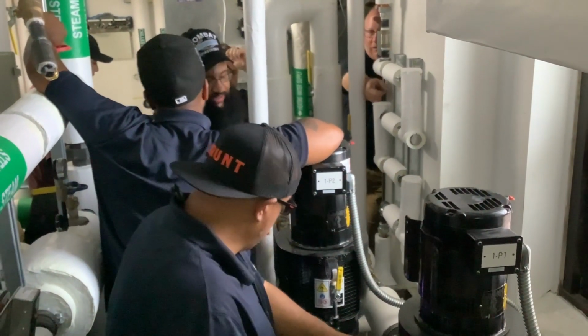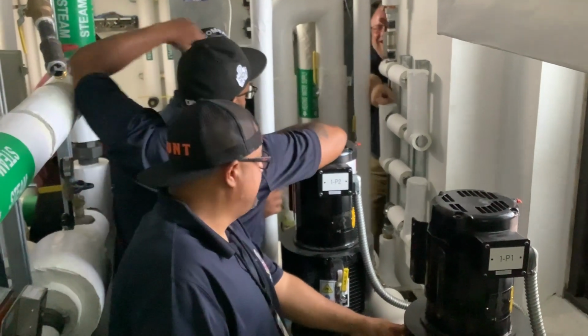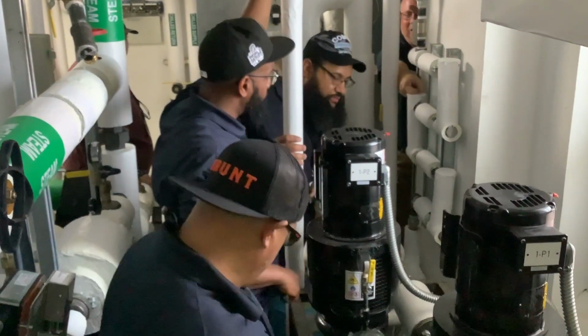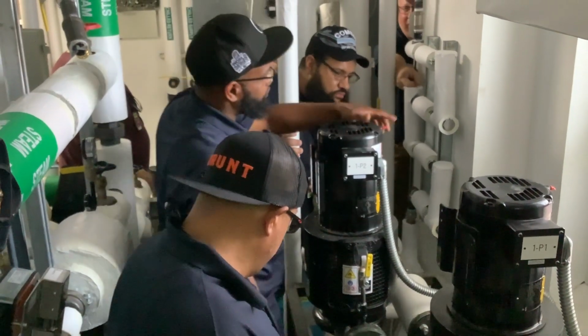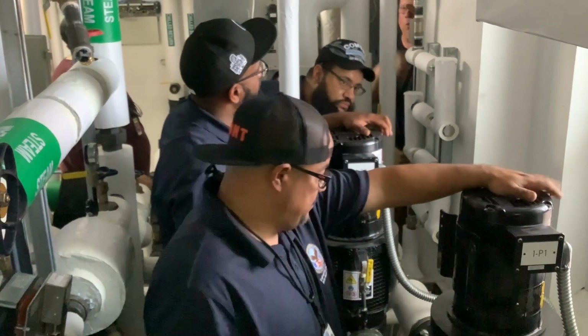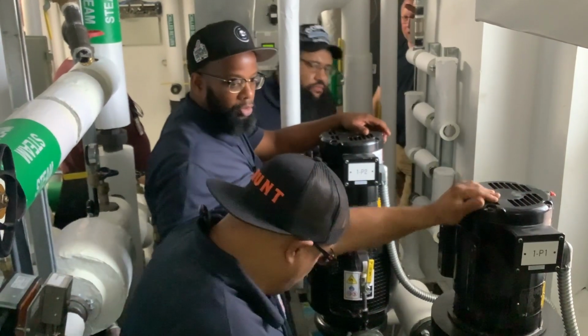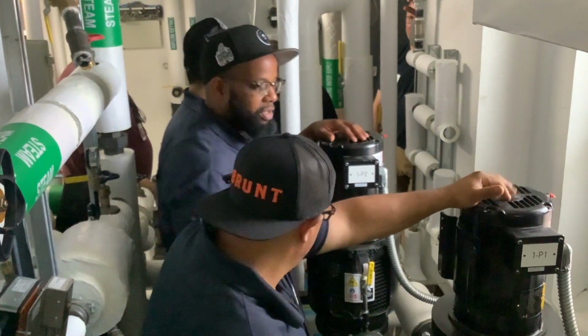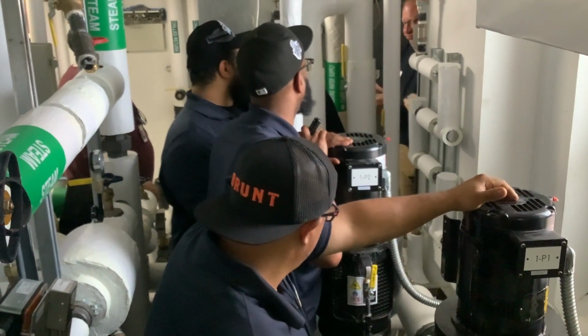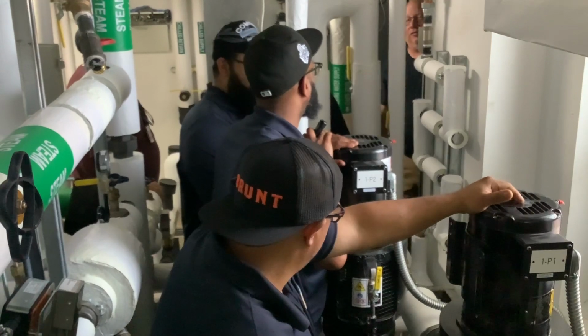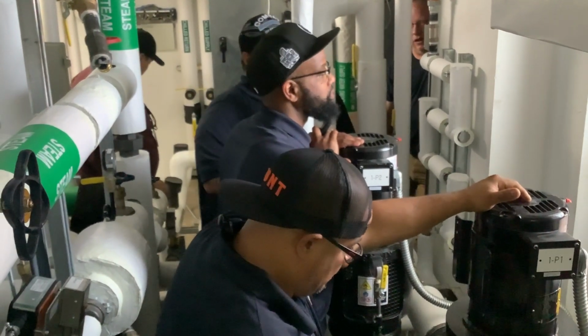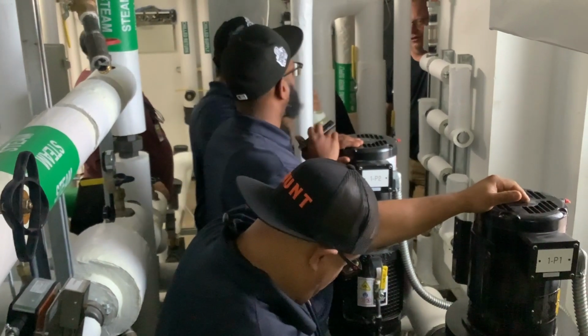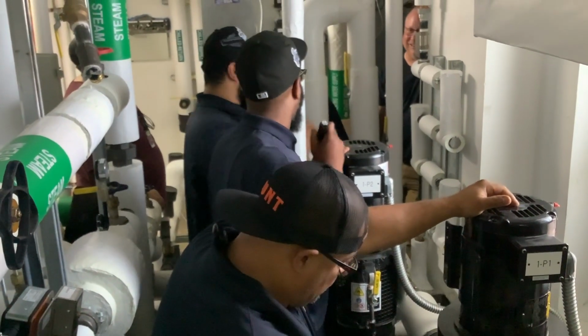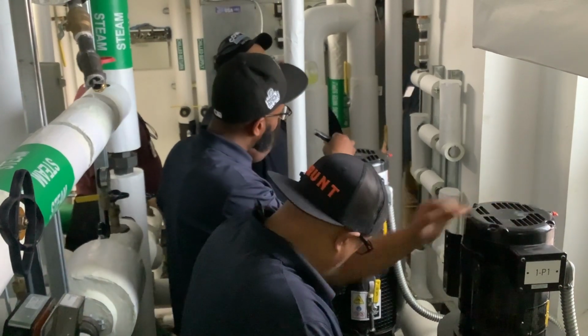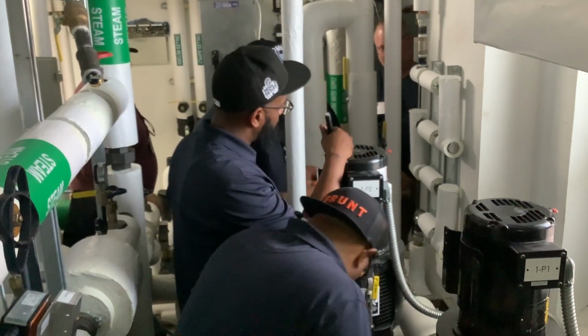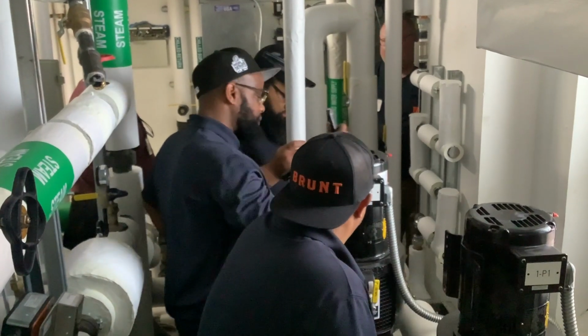After 4 or 5 years, they're going to run stuff through that isn't meant for it anyway, depending on how hard you're operating them. You see the red tops there, those are just grease reliefs. Once in a while, just grease one or two pumps at the most. Do not over-grease them, you'll burn out the motors. Normally once a year you're good to go. Don't be the over-greaser, I don't want to come back in a couple years and see these things all gummed up. So they don't require a lot, they're pretty good.